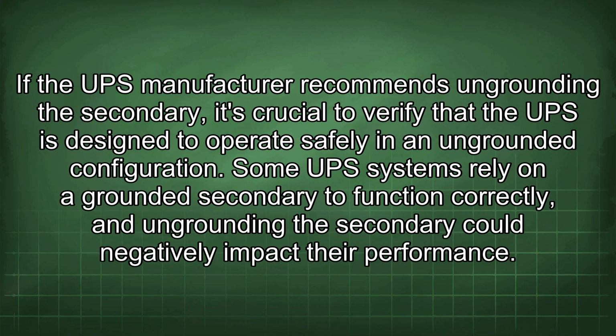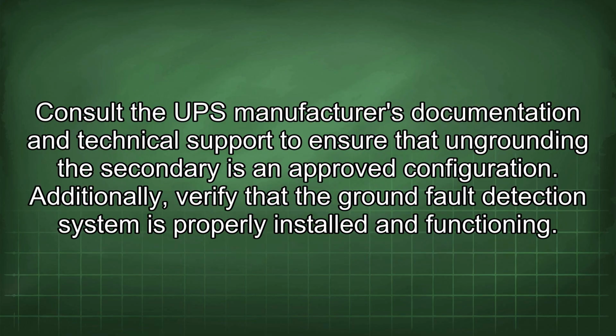If the UPS manufacturer recommends ungrounding the secondary, it's crucial to verify that the UPS is designed to operate safely in an ungrounded configuration. Some UPS systems rely on a grounded secondary to function correctly, and ungrounding the secondary could negatively impact their performance. Consult the UPS manufacturer's documentation and technical support to ensure that ungrounding the secondary is an approved configuration.